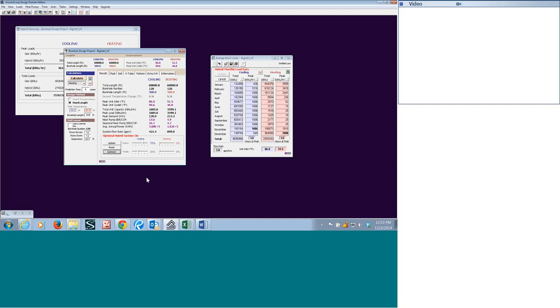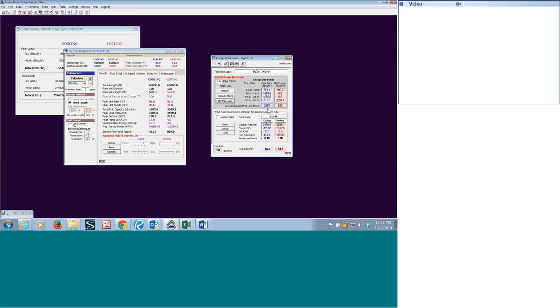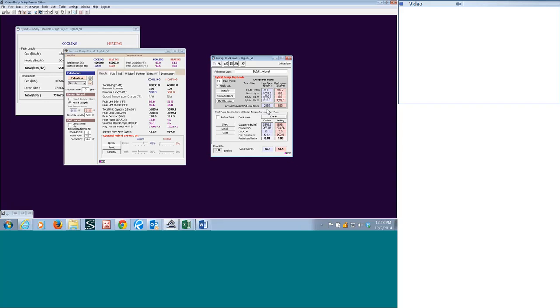Because the calculation for the full load hours is a proportionate value of the peak versus the total annual. So all it is, is a proportion. So, okay. So if I'm just reducing by 50%, then you're not going to change the full load hours. Right. So our peak full load reduced correspondingly. Yes, sir. Yeah, got it.